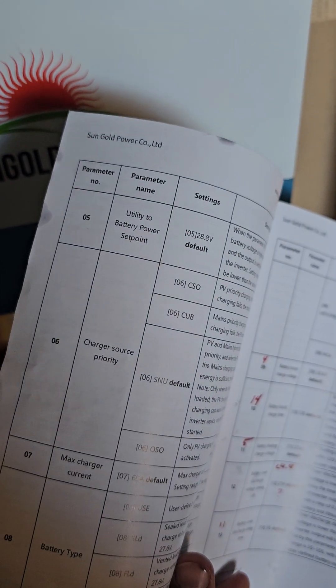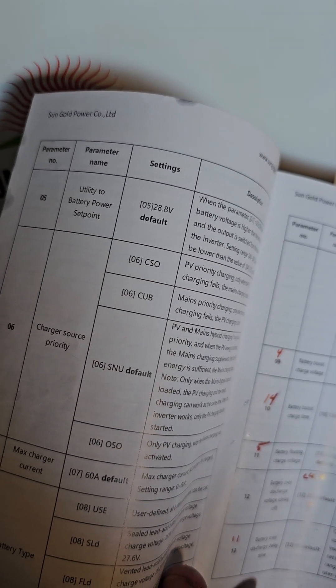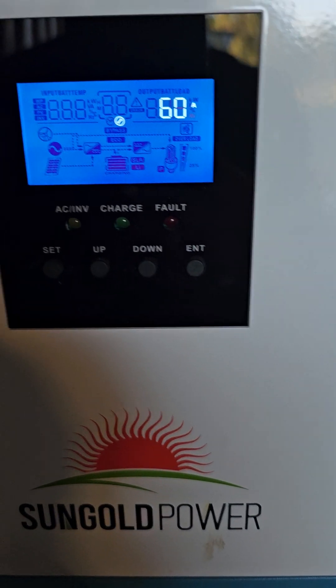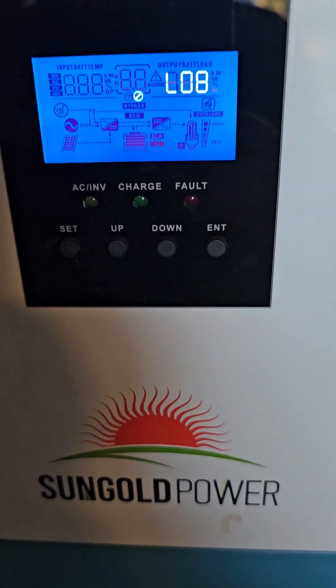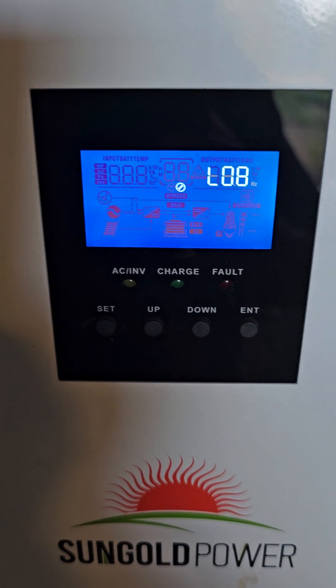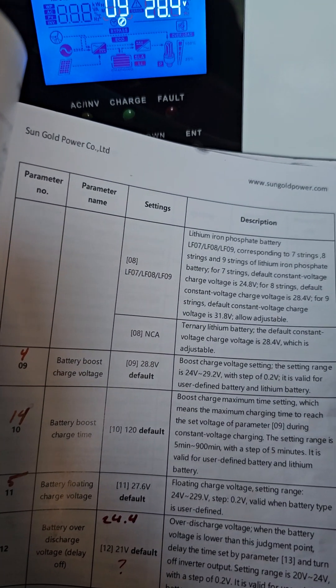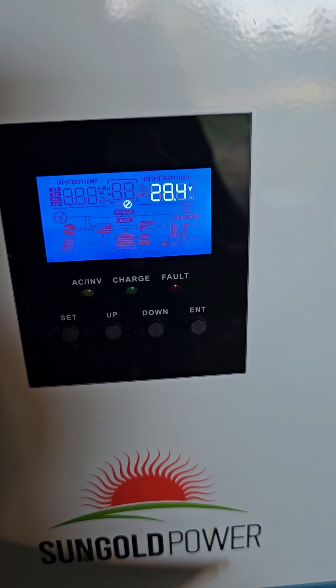Parameter five: utility power set point — by default it's at 28.8. That's fine, you can leave it where it is. Number six: same thing, I left it alone. Number seven: 60 amps — that's okay, not a problem at all. Number eight: that's what we talked about — we tried LF07 and it even worked on gel, but for whatever reason they were telling me it needs to be on lithium eight, so that's what we did. Number nine: 28.8 volts — that's not the default. They wanted me to change it to 28.4, and I did.